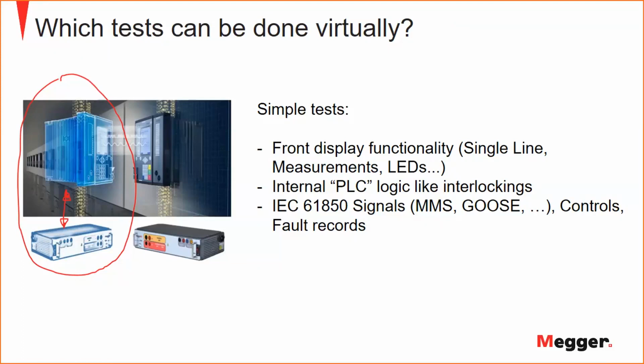Front display functionality, single line diagram, measurements, LEDs. Look that the measurement is correctly shown on the single line diagram. PLC logics like interlockings. They are easy to test, but they're complicated. They're long, but they're easy from the competence point of view, but they are tricky. 61850 signals, have a look at the correct MMS and correct GOOSE message is sent when the correct current, voltage or correct interlocking signal is received by the relay, and these signals are given by the test set, digital twin test set.